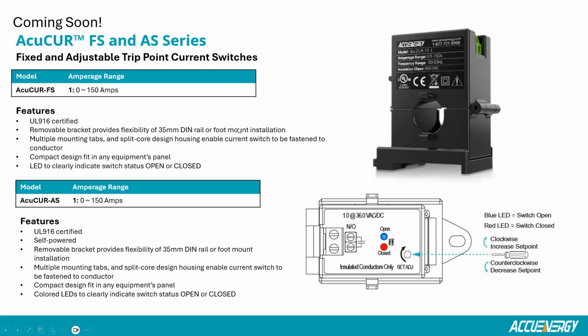A couple really nice features built into this one: it's UL 916 certified and has a removable bracket mounted to the base of the current switch. That bracket gives you the flexibility to mount the sensor to 35mm DIN rail or surface mount it via the single hole on the bracket, or you don't have to use the bracket at all and can directly mount the current switch to the conductor via the zip ties provided with the switch. It's got mounting tabs on this side and one on the other side.